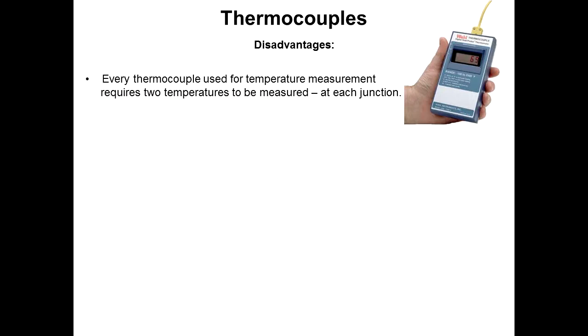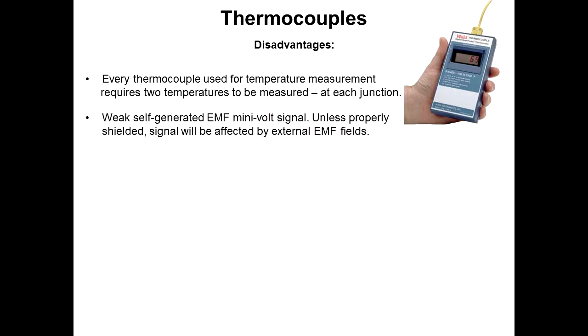Disadvantage: it requires two junctions, two temperatures to be measured, at the hot junction and at the cold junction. The signal is very weak in a thermocouple, so it's very subject to being interfered with by any outside electrical voltages, so it's required to be properly shielded. Never run thermocouple wire without proper shielding next to a big electric motor or something like that.